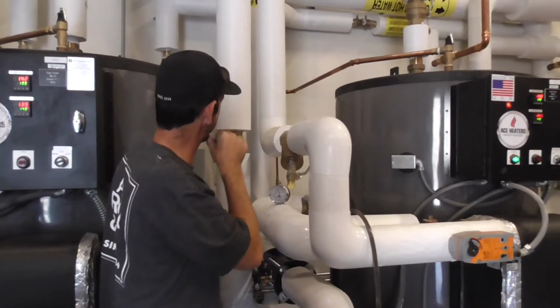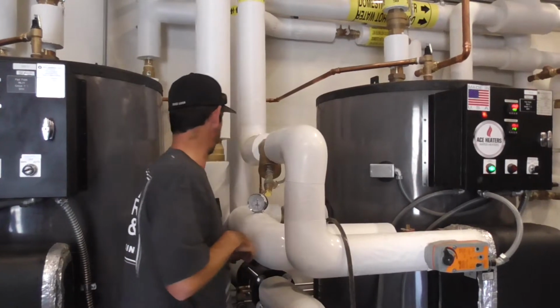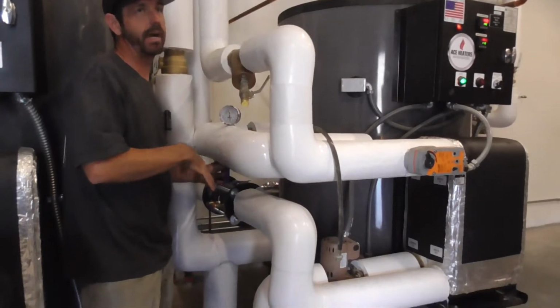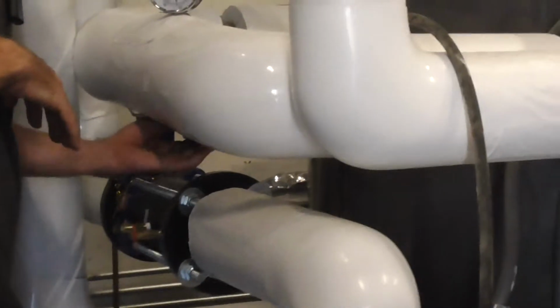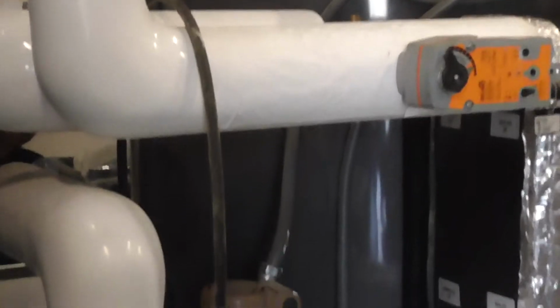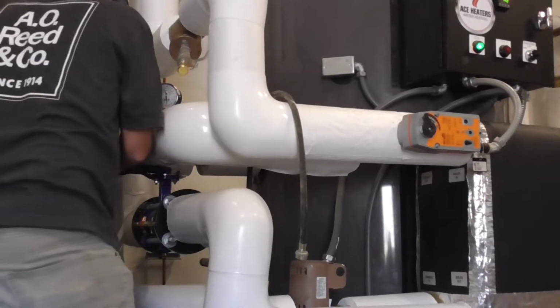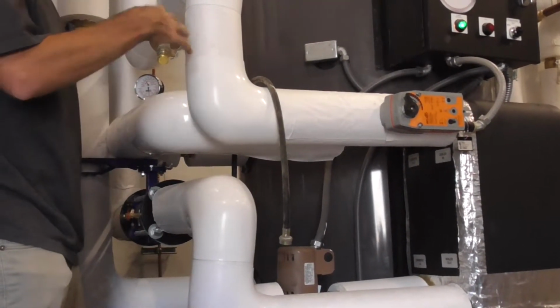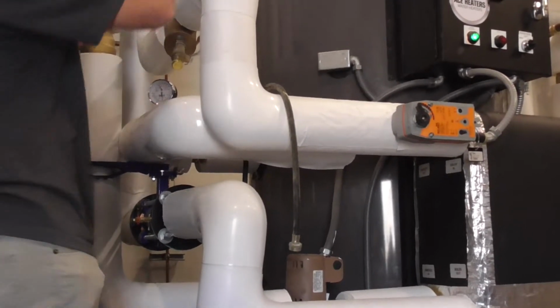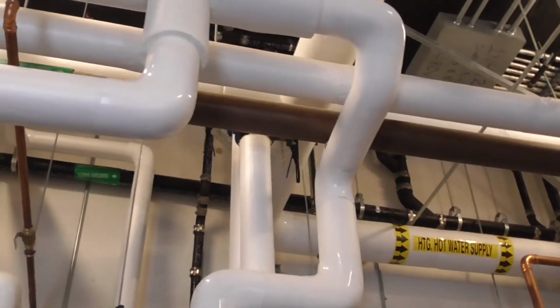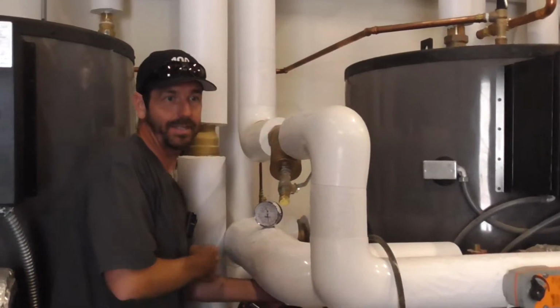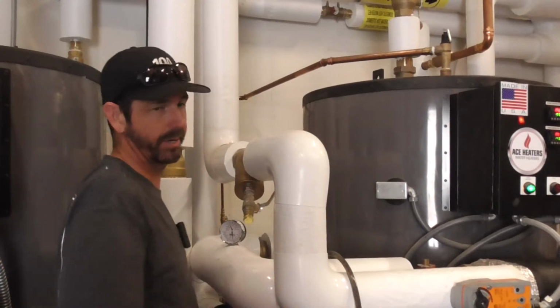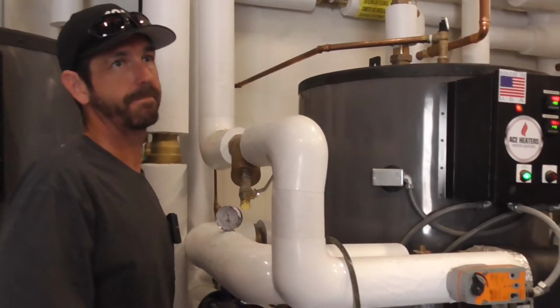So that's the domestic water side. The heating hot water side, we have a balancing valve here on the return. If you're just trying to stop flow to the unit, you can shut this valve, right? This down here. But if you're trying to drain the heating hot water side of the unit, close this, and now we won't have heating hot water flow, but we can't drain it yet. Okay, if you got to drain it, you got to shut the valves off. But if you're just trying to stop flow on the heating side, if the control valve's not working, you shut that valve. Does that make sense? Yep.